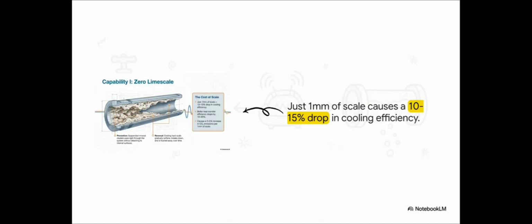And on a day-to-day operational level, it's a total financial disaster. Just one millimeter of scale, a layer thinner than a dime, triggers a massive 10 to 15% drop in cooling efficiency. If you're operating chillers for a giant commercial building or managing strict temps for semiconductor chip manufacturing, your heat exchangers are suddenly trying to work through a layer of stone.